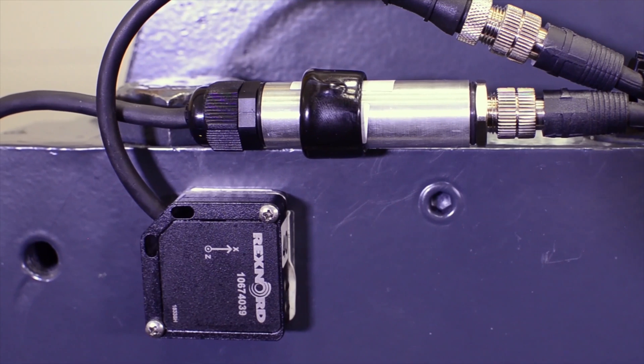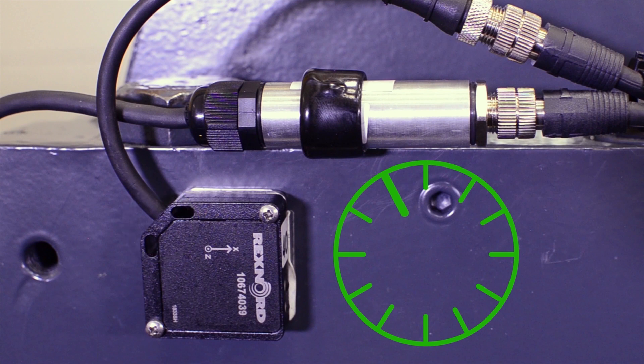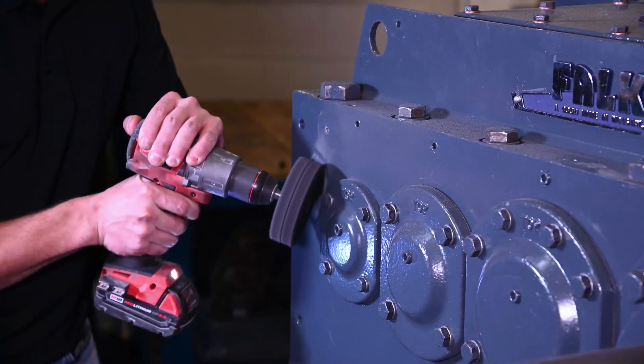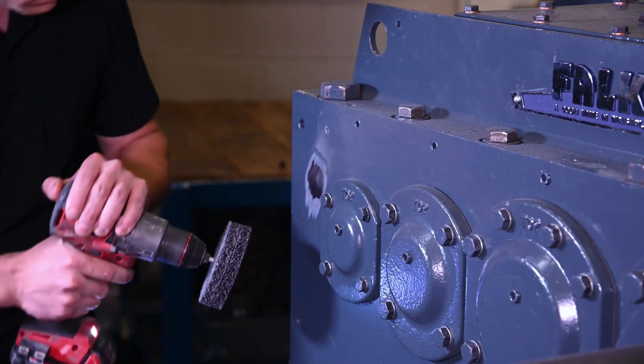When installing, orient the sensor so that the angled edge of the sensor is located at the 11 o'clock position. There is also an x-axis marked on the sensor. Ensure that the x-axis is parallel to the split line or top of the housing.